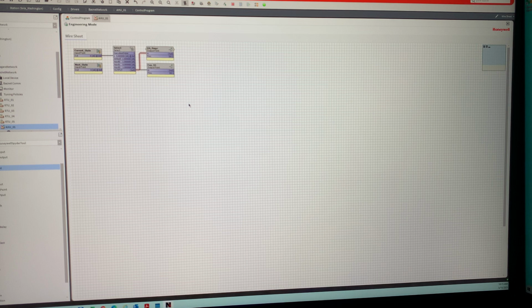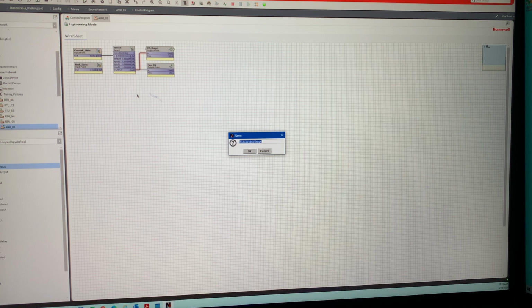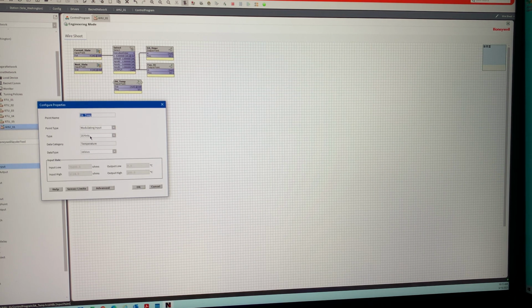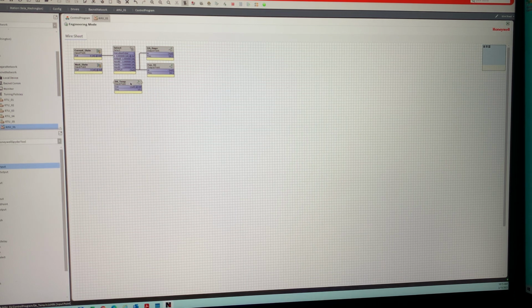Now we need to work on a discharge air temp. So for this one, what we're going to do is we're going to do it based on a DAT versus maybe climate control, things like that. So we're going to do our modulating input. We're going to call this DA temp. So we're going to go here, go to configure properties. I'll bring this over for you so you can see it. It's going to be a 20K sensor. There's the TR20 series, which is the normal zone temp sensors, but everything's going to come in as a 20K. And then we like to set these up for Fahrenheit. Click OK. And there we go. So now our DAT temp is set.